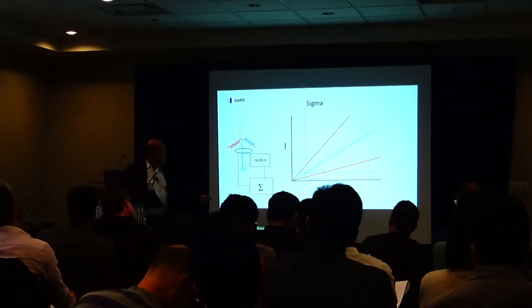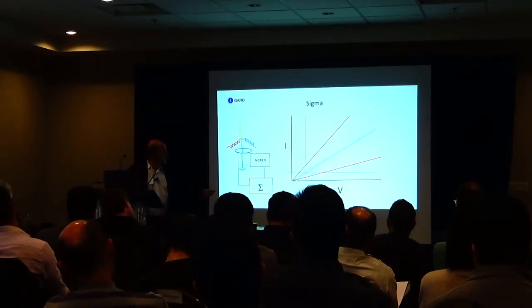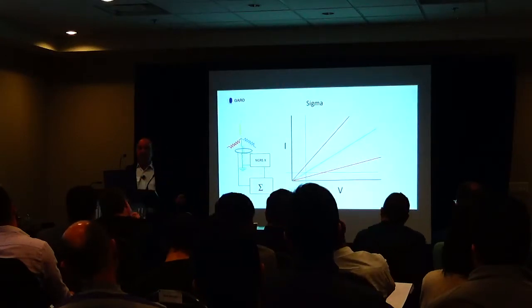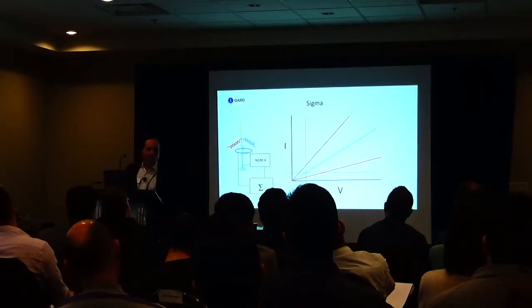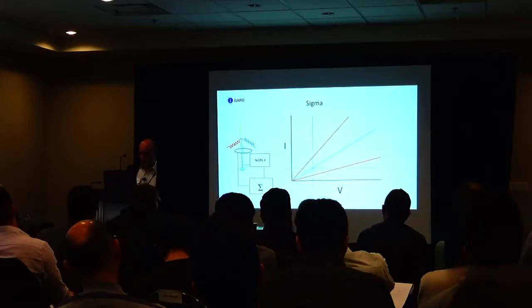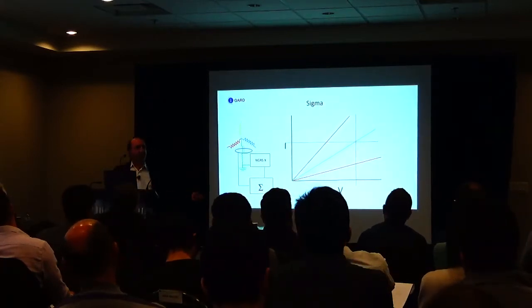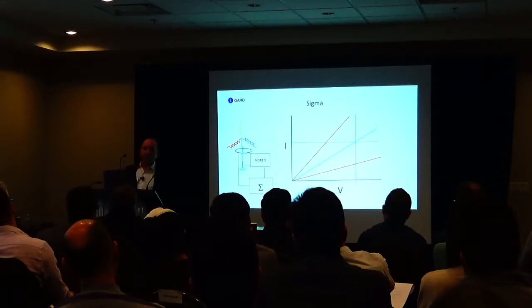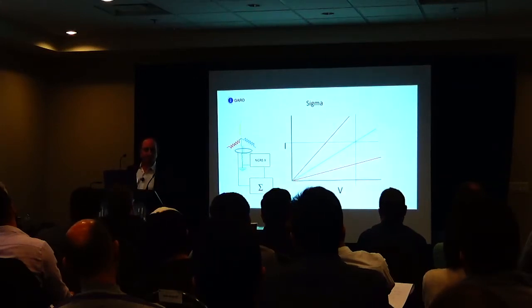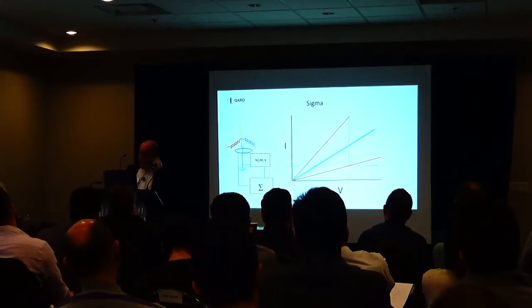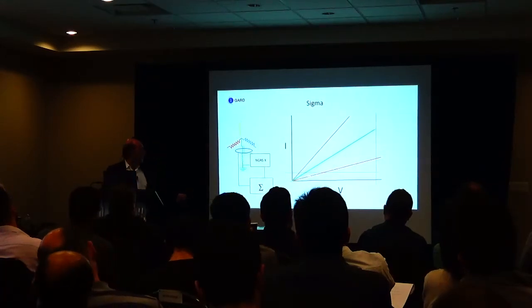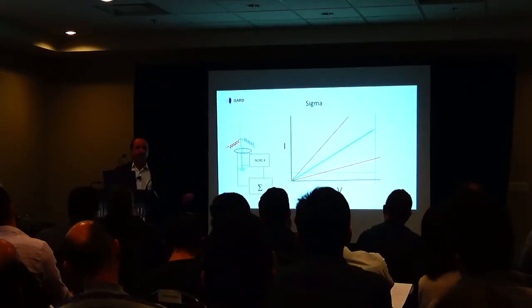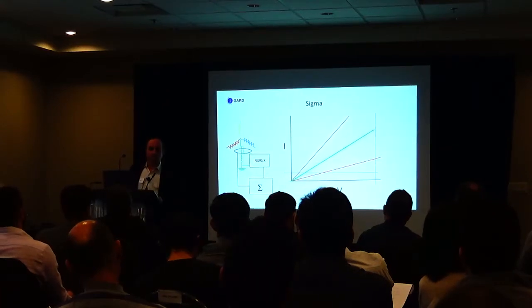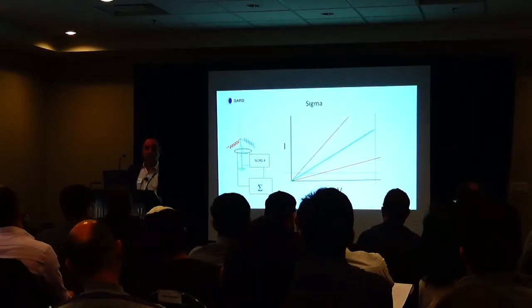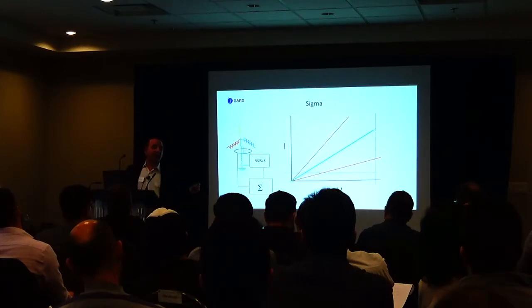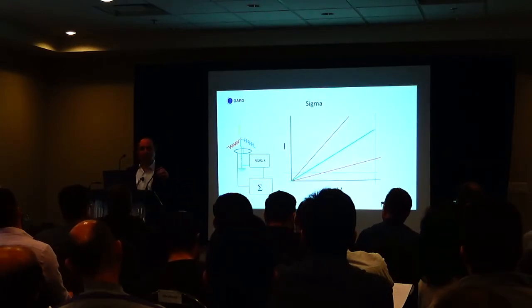We get this value for voltage, we get this value for current. This green line is the line that it should follow if your resistor is okay. You get a fault, current goes up, resistance stays the same, voltage goes up. Say for example, there's something wrong with your resistor: voltage goes up, current doesn't increase. You have an open circuit. There's a problem with the resistor. And this is only when you have the capability of measuring voltage and measuring current.